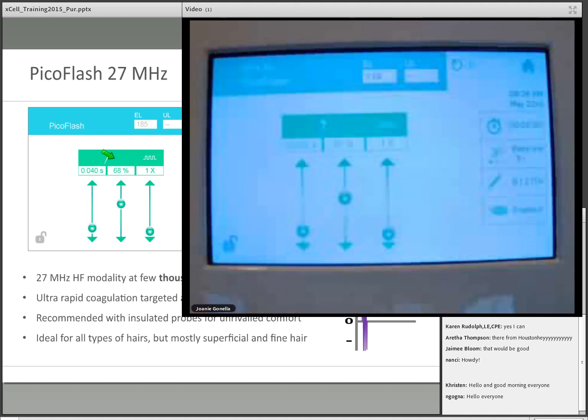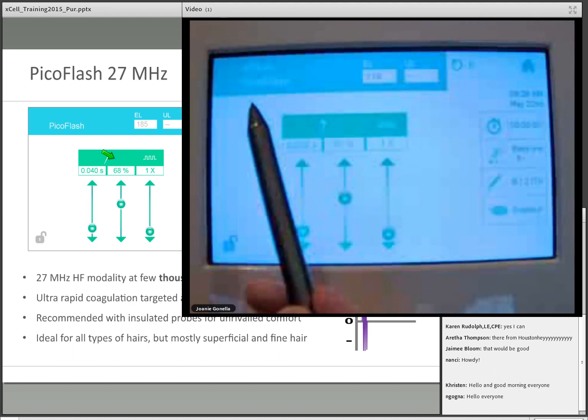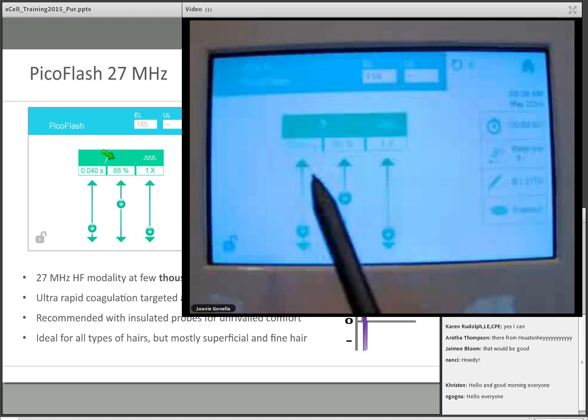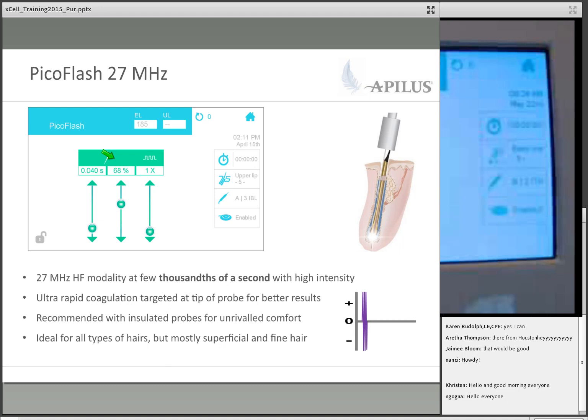So on my treatment screen with Picoflash, essentially this modality is in thousandths of a second, and that is high intensity. High intensity is usually something that will be above 60%. So if we go back to our PowerPoint, if you're flipping back and forth, look at the time, look at the intensity. This is the time and intensity for this preset here. So we have 3 spots after the decimal, so 0.040, which is 40 thousandths of a second. And this is our intensity, which is 68% in this case here.